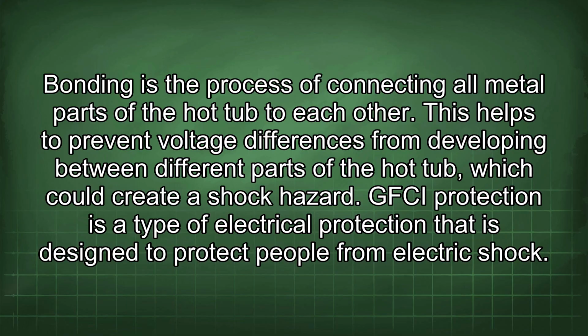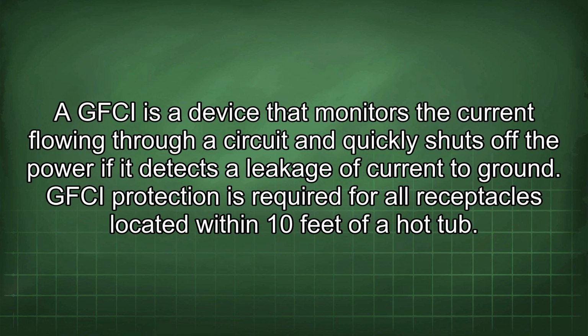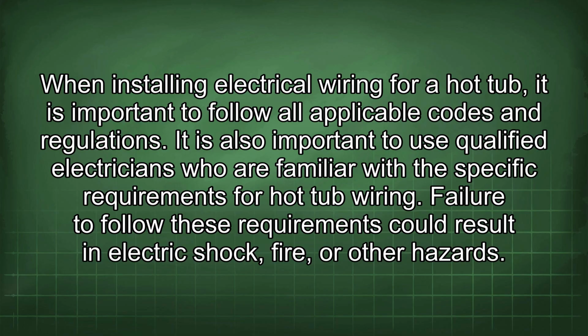This helps to prevent voltage differences from developing between different parts of the hot tub, which could create a shock hazard. GFCI protection is a type of electrical protection that is designed to protect people from electric shock. A GFCI is a device that monitors the current flowing through a circuit and quickly shuts off the power if it detects a leakage of current to ground. GFCI protection is required for all receptacles located within 10 feet of a hot tub. When installing electrical wiring for a hot tub, it is important to follow all applicable codes and regulations. It is also important to use qualified electricians who are familiar with the specific requirements for hot tub wiring. Failure to follow these requirements could result in electric shock, fire, or other hazards.